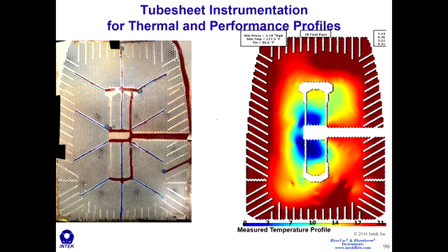And so here's a unit that we monitored. This is a De Laval condenser. Over on the left you can see photographs that I've stitched together of the outlet tube sheet. You can see some instruments that we've installed at these locations here and here. This is during the installation process, so there are still some tools on the tube sheet that will be removed.